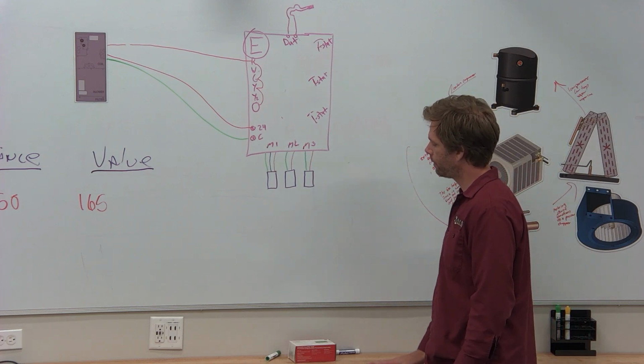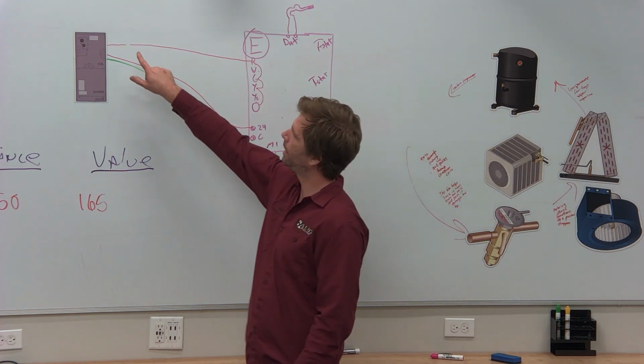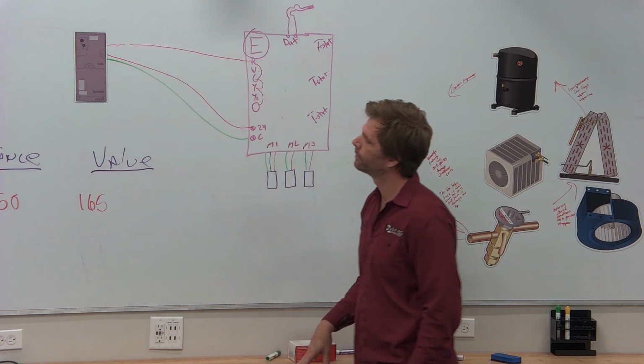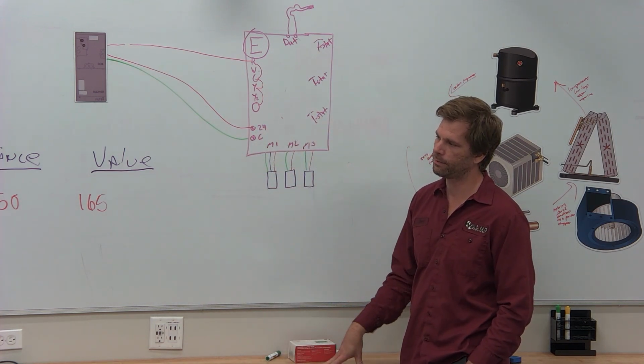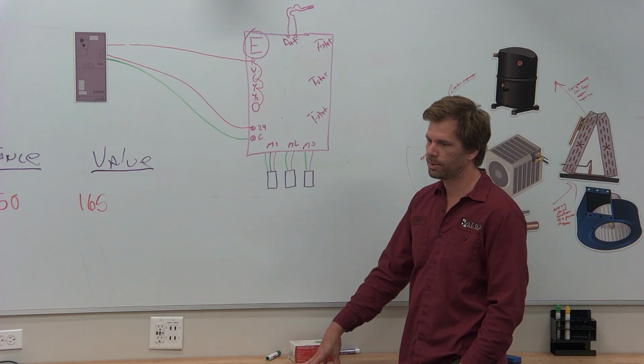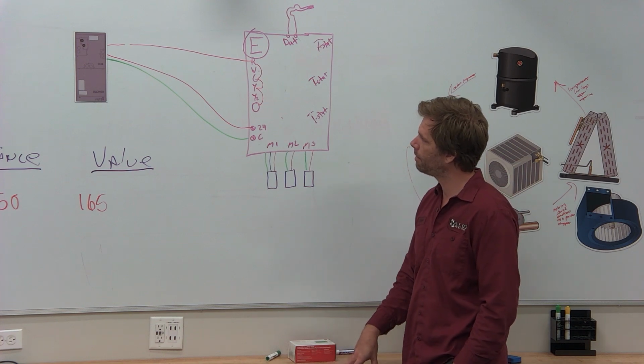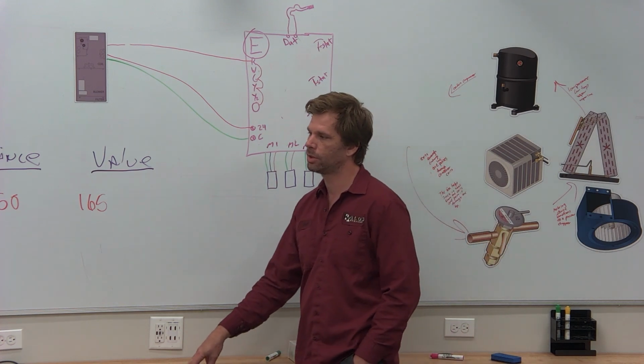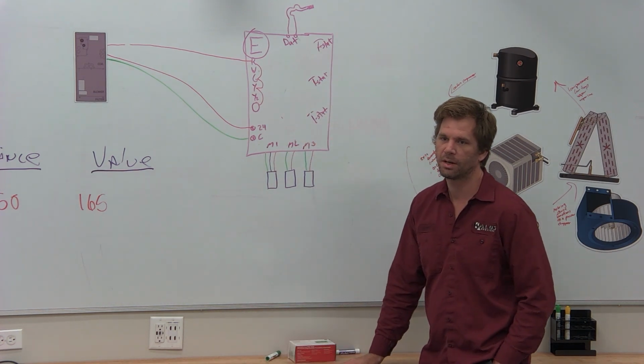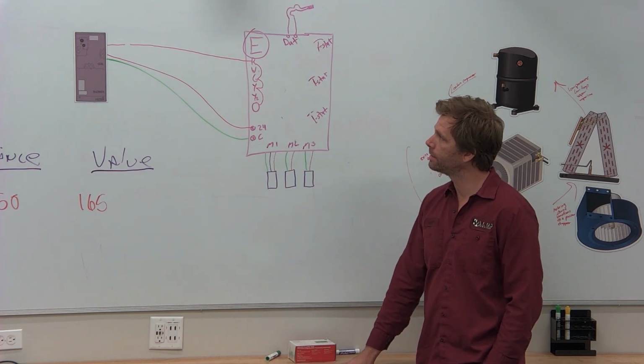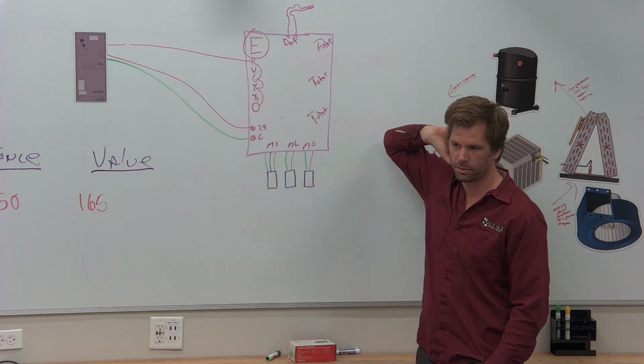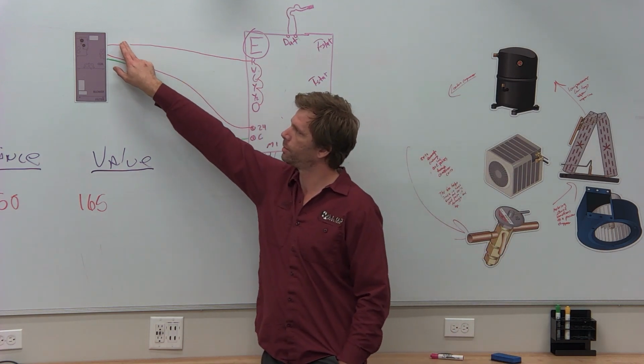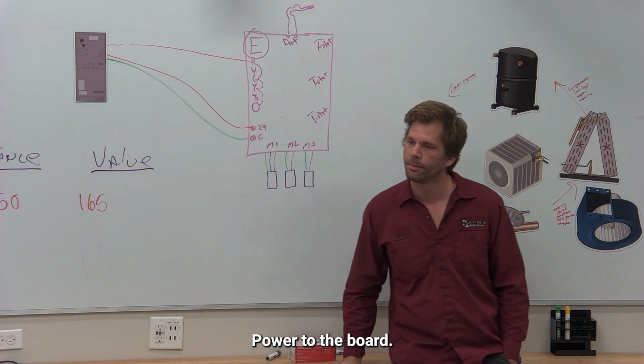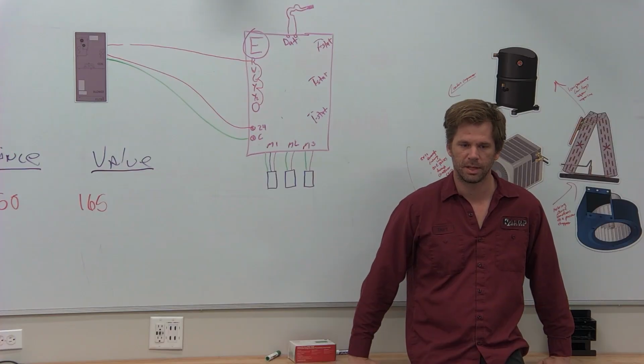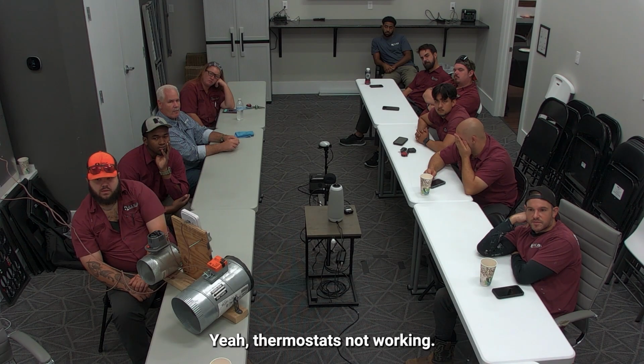I get a lot of calls where red is broken by a fuse or a float switch. Again, something we already understand. It's very simple. But I'm getting a call from someone who's been there 30 minutes trying to figure out what's going on because they didn't check the float switch or the fuse, some very basic things. Why in this situation were they not looking at the float switch or the fuse if, let's say for instance, the float switch is tripped and red is broken right here? There's power to the board, yeah. Which in their experience, what are they seeing? It's making them think that it's not a float switch. Yeah, thermostats not working.